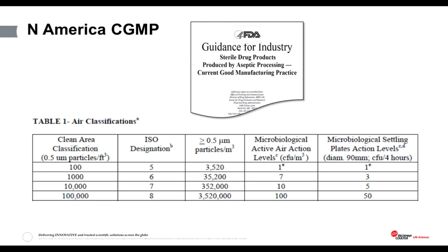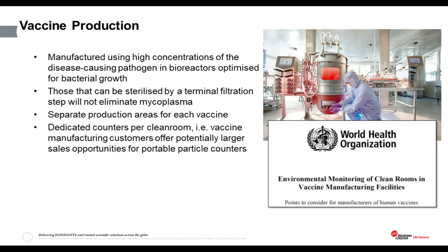Let's take a look at the North American CGMP document. It differs from the European and World Health guidance in that it only mentions one particle size — the 0.5 micron particle. However, any manufacturer based in North America wanting to sell their products outside of North America will have to count both the 0.5 and 5 micron particles, as they must be in compliance with the standards of the country to which they want to export their products.